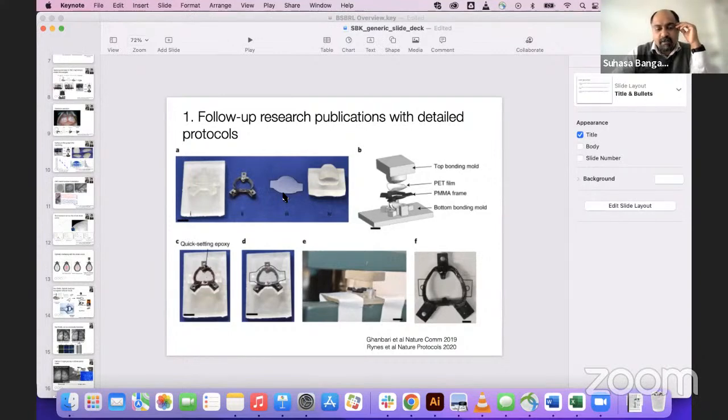So that's one. The second thing is, as compared to glass, these polymers absorb some of the blue wavelengths, and there's a little bit of autofluorescence. So when we do two-photon stacked imaging, you can see a thin layer of the polymer coming up in your two-photon Z stacks. And there's about 3 to 5% greater loss in the power of the light that can be transmitted through these polymers as compared to glass cover slips.